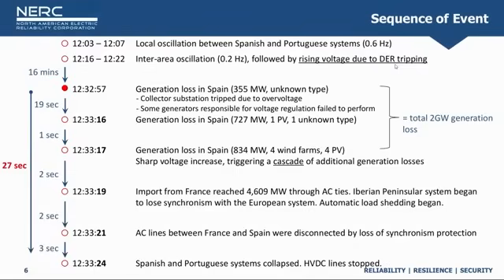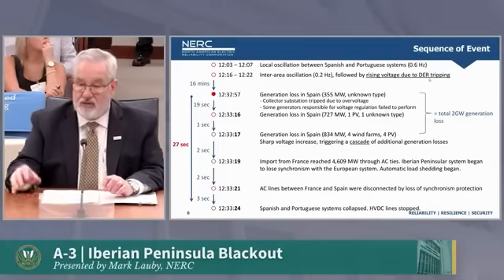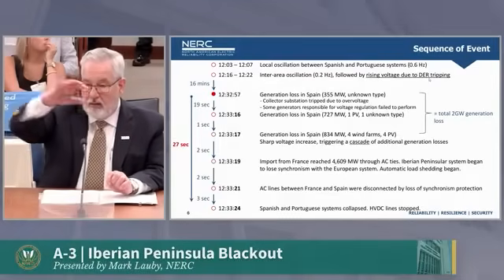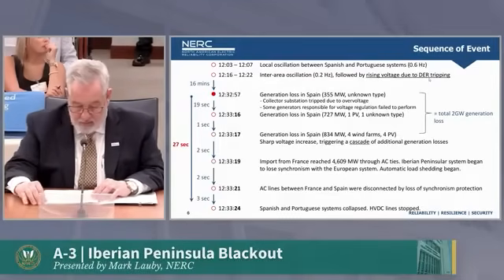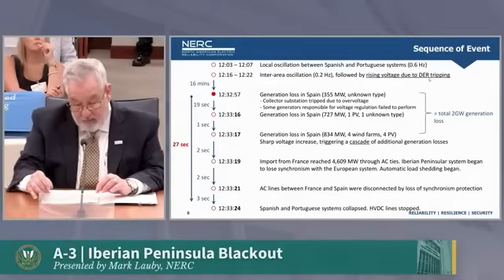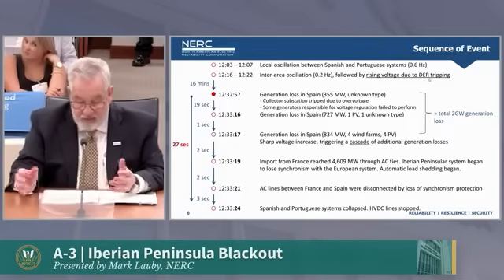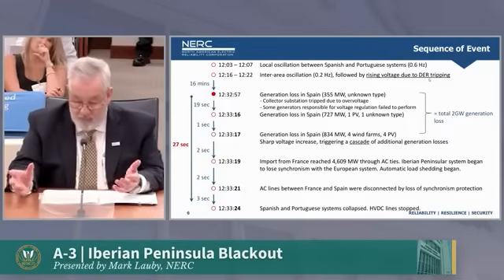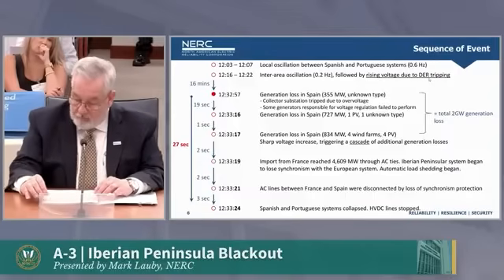Half an hour before the blackout, there were two significant oscillations causing a decrease in average voltage. The first was a locally forced oscillation, according to the Spanish report - there's still more to learn there. The second was the inter-area oscillation, which rings between Turkey all the way across the continent. Similar inter-area oscillations occurred in 2016, 2022, and 2025, but they didn't end up causing a blackout.